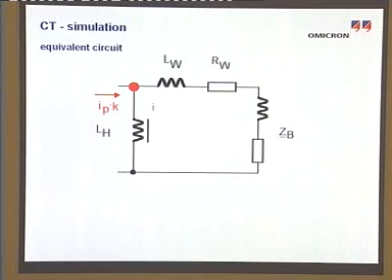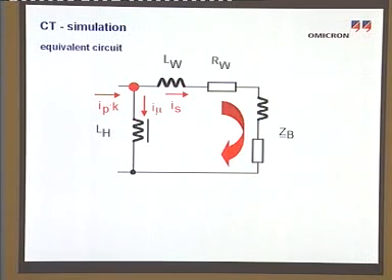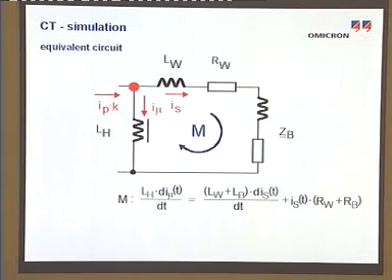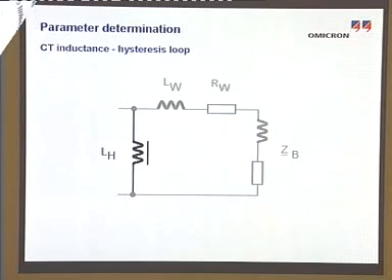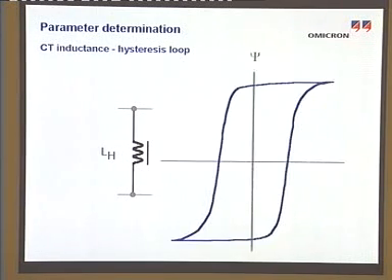According to Kirchhoff's law at the red node, the secondary current is merely the image of the primary current distorted by the magnetizing current. The secondary current is of special interest because it flows through the relay. It can be calculated via the mesh M and Kirchhoff's law. Special attention has to be paid to the magnetizing inductance. When having a closer look at this quantity, it becomes obvious that it is a non-linear element due to the magnetic behavior of the iron core, known as the hysteresis loop.